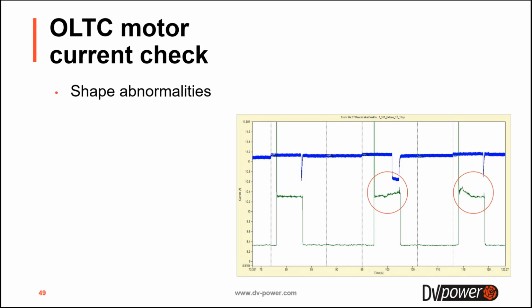In this graph here, you can see the two problematic transitions that are represented with the red circles. So you have shape abnormalities in the motor current. The motor current should look like in the first transition here: you have a high inrush current, and then you have pretty stable motor current. But if in some transition the motor current is not stable, that means the motor needs some extra energy to deliver to the mechanism. That means the mechanism has some problems.